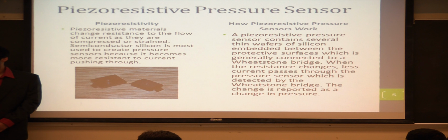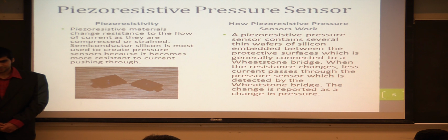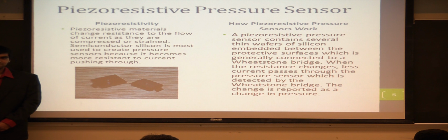An important thing to note about the silicon substrate used for the diaphragm is that as a pressure is applied, the resistance to a current passing through increases substantially, and it allows less current to pass through, and with less current passing through, less heat is generated, which allows our bioinstrument to be less heat sensitive, which Parker will go over during our disadvantages for the slides.